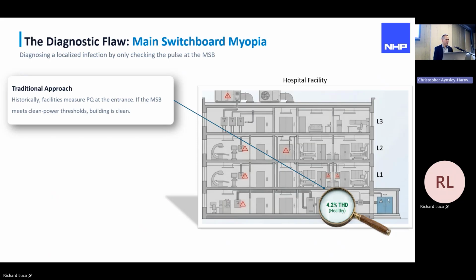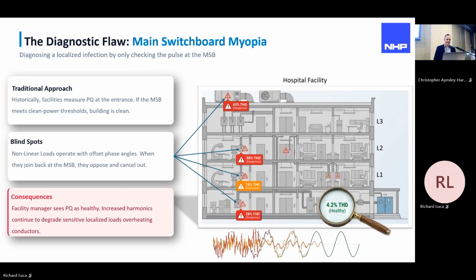So the traditional approach, we put an energy meter at the main switchboard and we see, okay, 4.2%, it's healthy, it's all good. And we see clean energy. But there's a lot of blind spots in that approach. Without monitoring individual loads, we don't know if there's harmonics that are propagating throughout the network and affecting other loads. So this can be causing a lot of issues deep within the network. And by the time it cancels out at the PCC, everyone thinks it's okay.